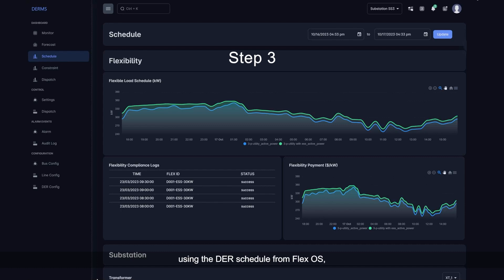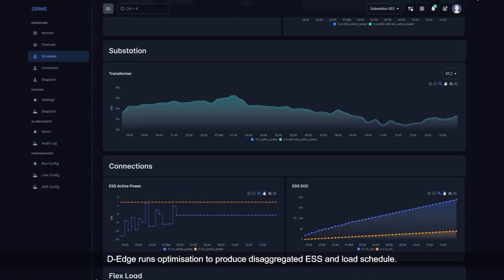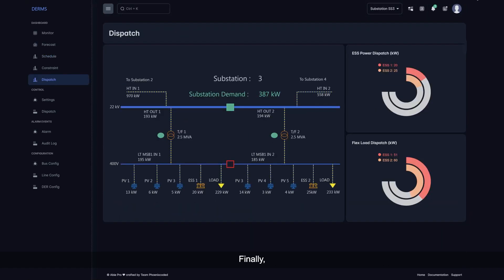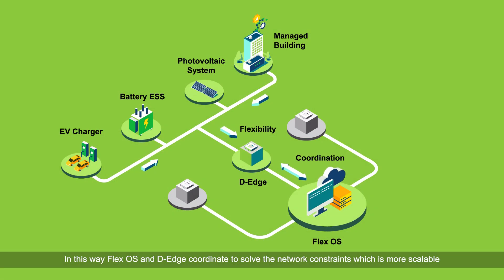In step three, using the DER schedule from FlexOS, D-Edge runs optimization to produce a disaggregated ESS and load schedule. Finally, D-Edge dispatches the immediate next 30-minute schedule to the ESS and flexible load. In this way, FlexOS and D-Edge coordinate to solve the network constraints, which is more scalable and provides real-time control at the edge.